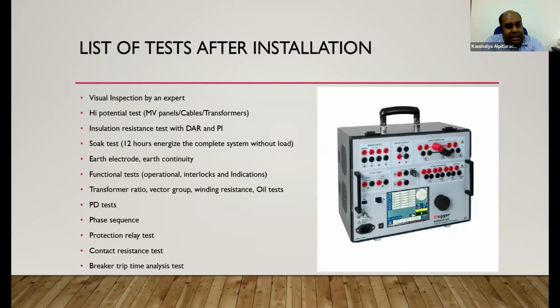Visual inspection by an expert, high potential test, insulation test with DAR and PI. DAR is the ratio between insulation resistance at 30 and 60 seconds. PI is 1 minute and 10 minutes. A soak test for 12 hours. Earth electrode and earth continuity test, functional test for operational interlocks and indications, transformer ratio, vector group, winding resistance, and oil related tests, maybe oil BDV, DGA, moisture level, dielectric, other tests, and so on.